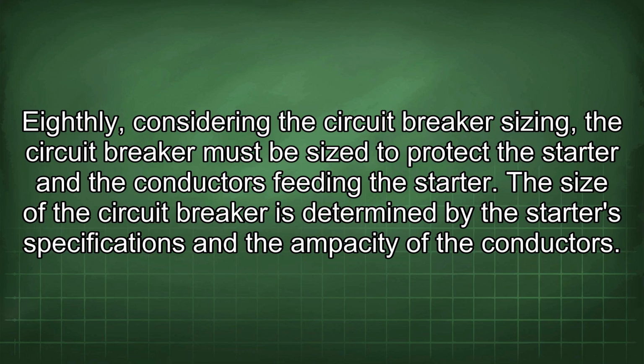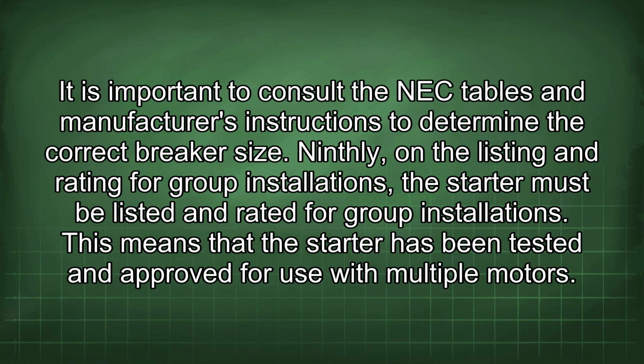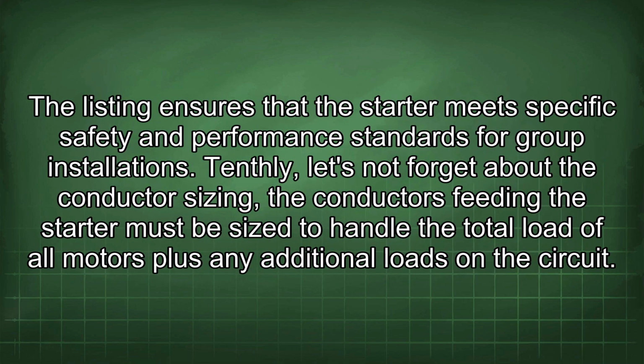The size of the circuit breaker is determined by the starter's specifications and the ampacity of the conductors. It is important to consult the NEC tables and manufacturer's instructions to determine the correct breaker size. Ninthly, on the listing and rating for group installations, the starter must be listed and rated for group installations. This means that the starter has been tested and approved for use with multiple motors. The listing ensures that the starter meets specific safety and performance standards for group installations.